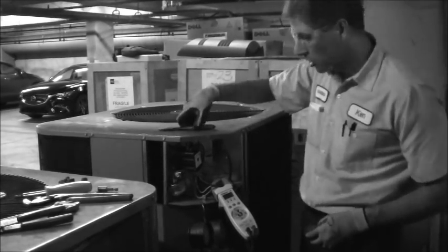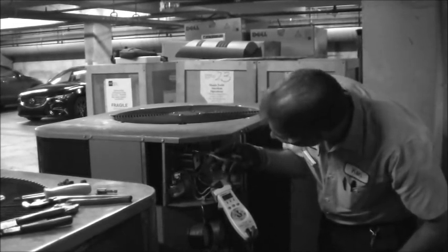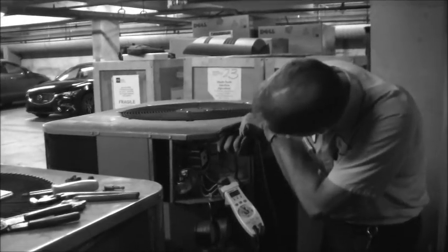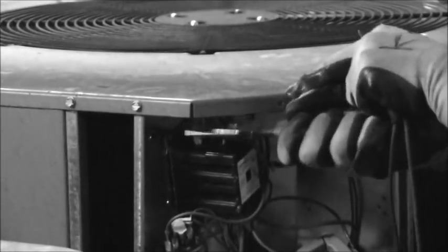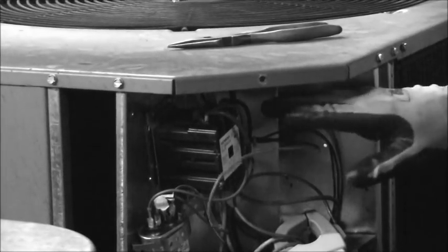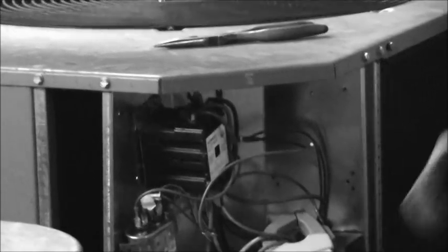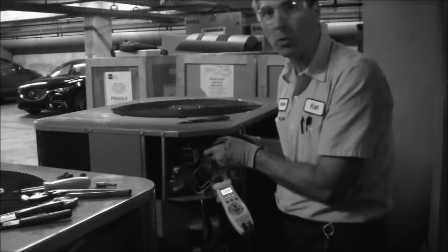So what I'm going to do is lift up one of the wires that goes to the condenser fan motor, taking that out of the system. So now I have only one wire landed on the condenser fan motor. Let's see if I receive equal readings for the compressor. This is phase A to phase B. 5.1. Phase A to phase C. 4.0. That's not equal. On a three-phase compressor, normally you would get equal readings.